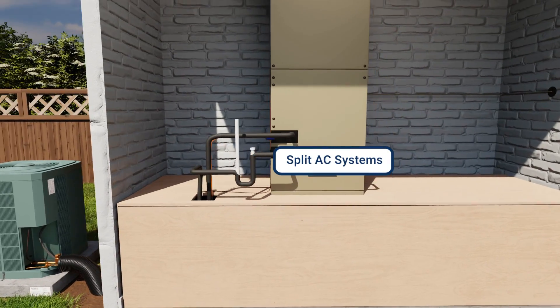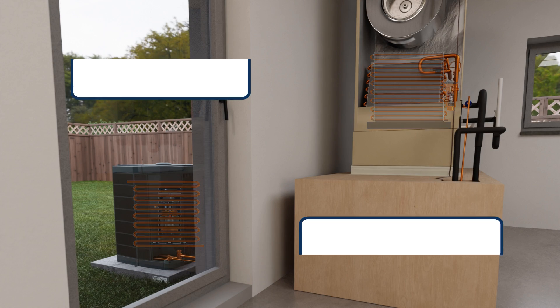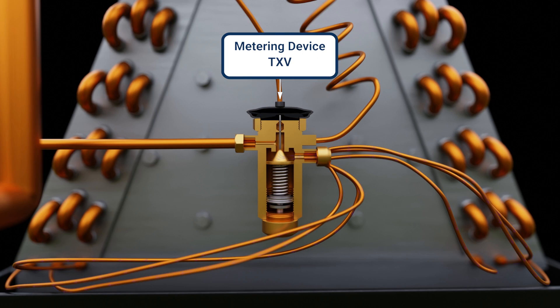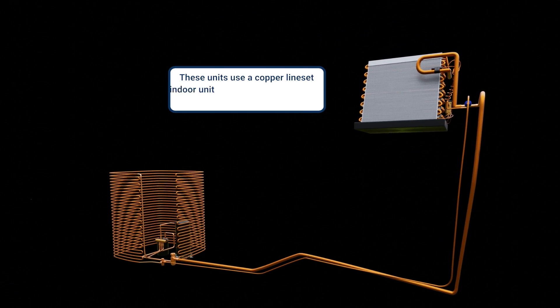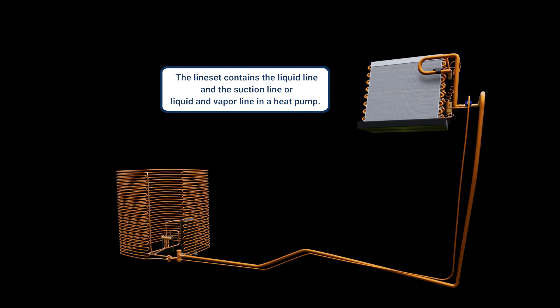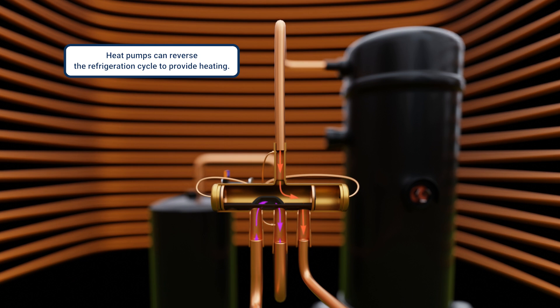Split AC systems and heat pumps consist of two main parts: an outdoor unit containing the compressor and condenser, and an indoor unit featuring the evaporator and, generally, the metering device. These split system units use a copper line set to connect the indoor unit to the outdoor unit. The line set contains the liquid line and the suction line, or the liquid line and the vapor line in a heat pump, because heat pumps can reverse the refrigeration cycle to provide heating in addition to cooling.